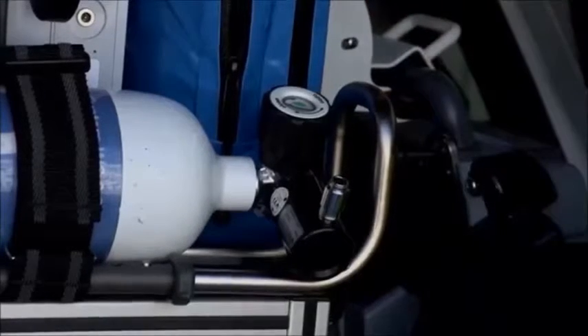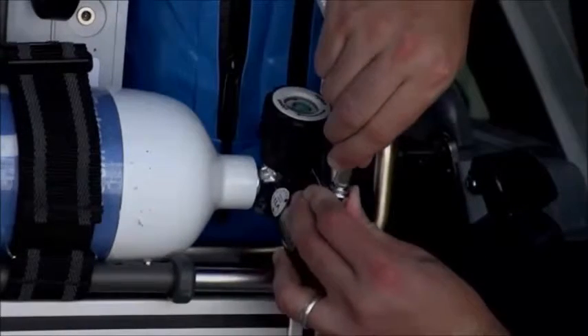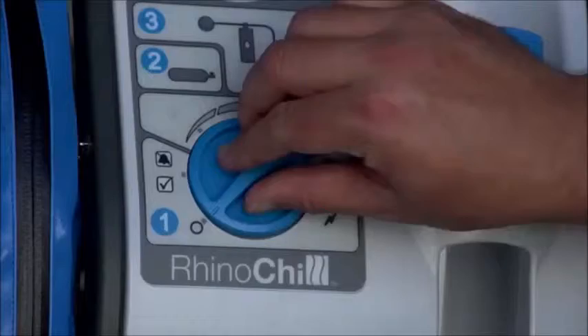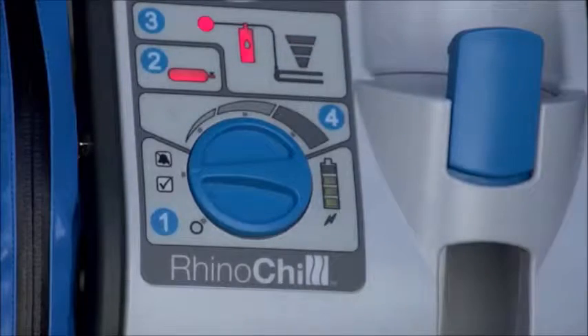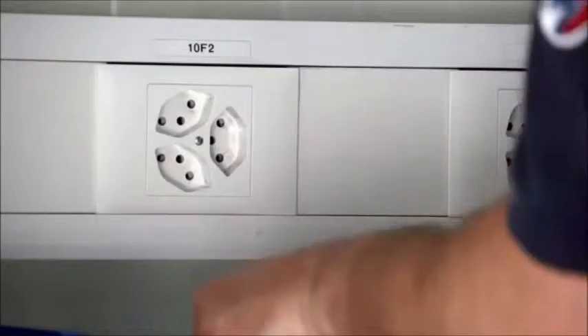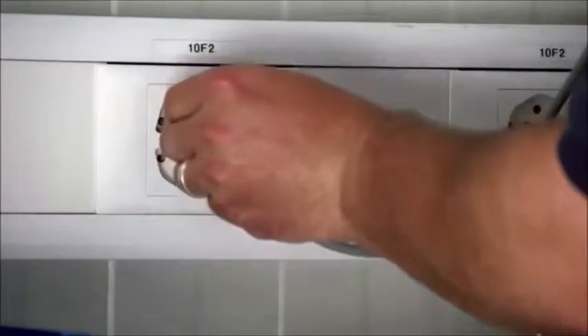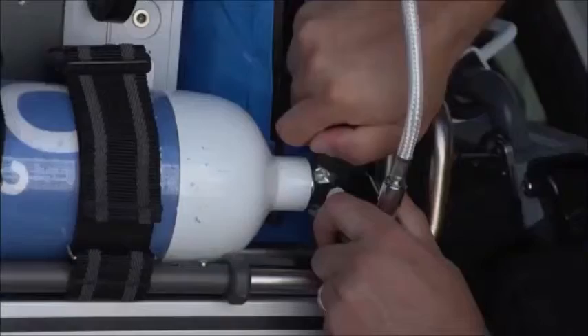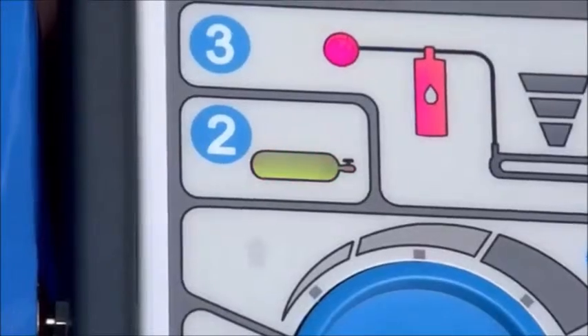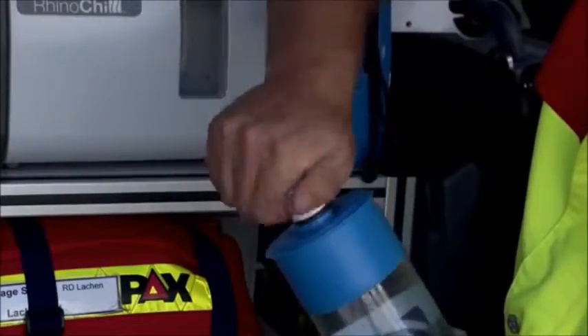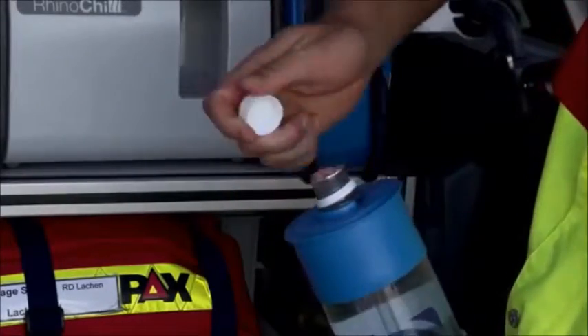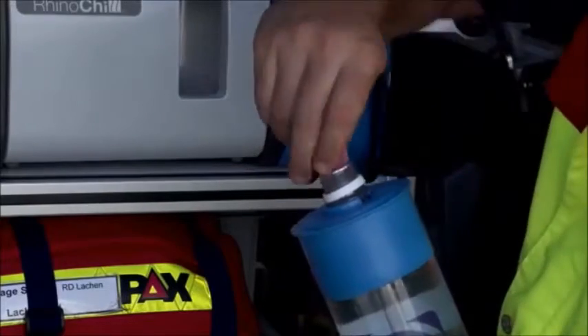If you've not already done so, connect the control unit to the pressurized gas supply. Turn the setting control knob to the check position. The battery light should illuminate green. If the battery light illuminates yellow, plug the control unit into an external power supply to recharge the battery. Open the gas supply valve and the gas cylinder light should illuminate green. Remove the cap from the coolant bottle, but retain it for use when disposing of the bottle. The simplest place for this is in the accessory bag pocket.